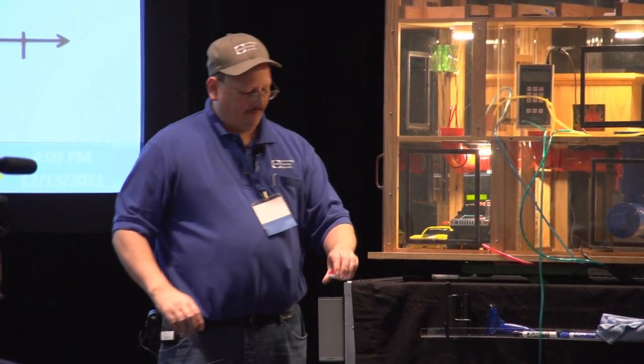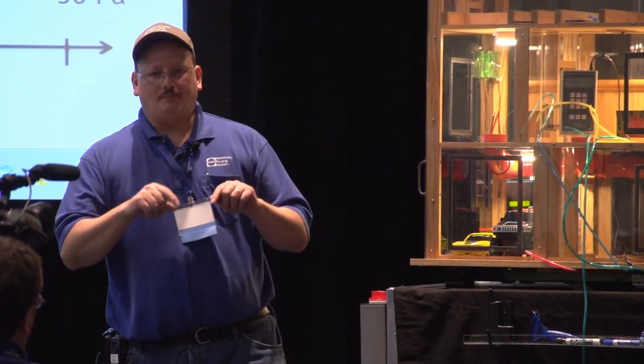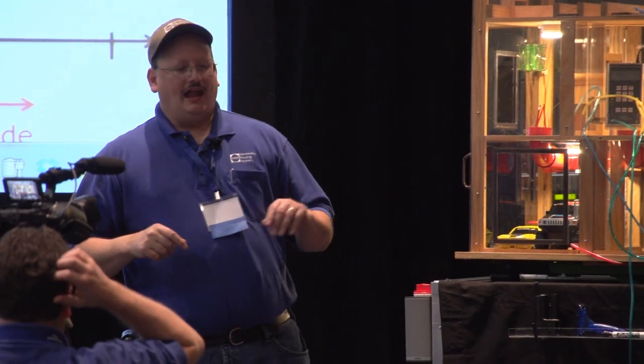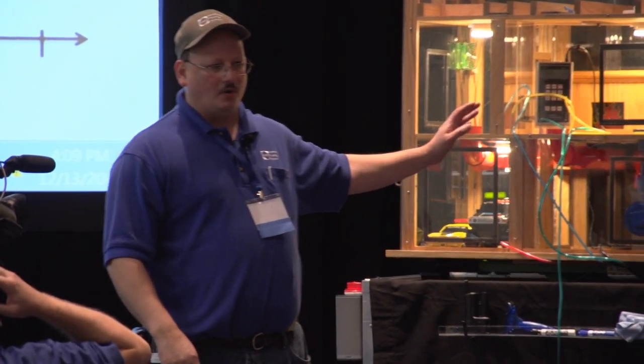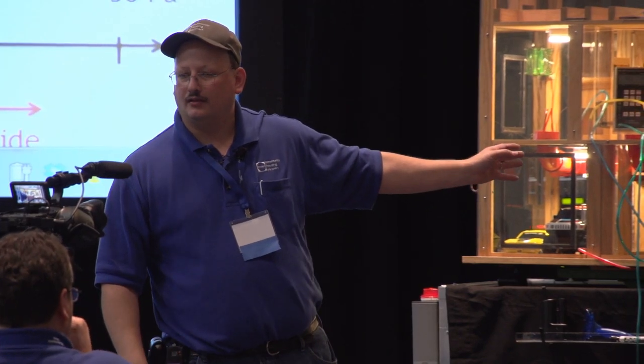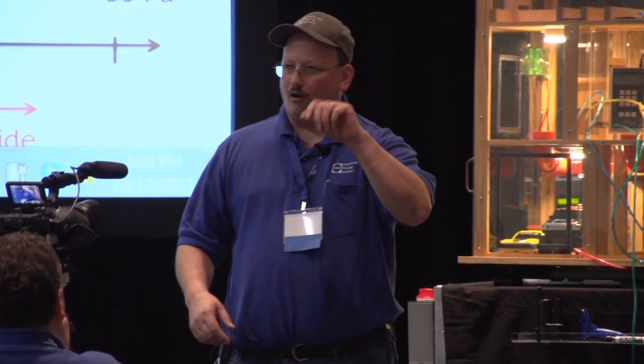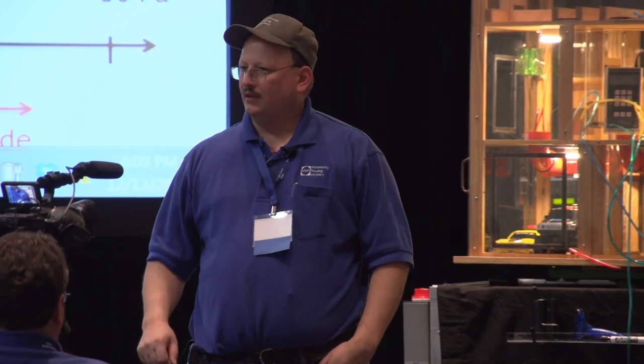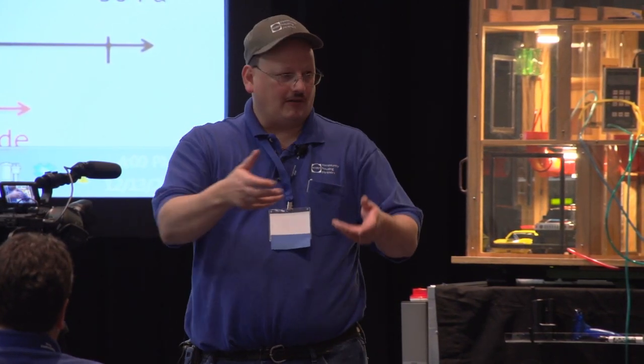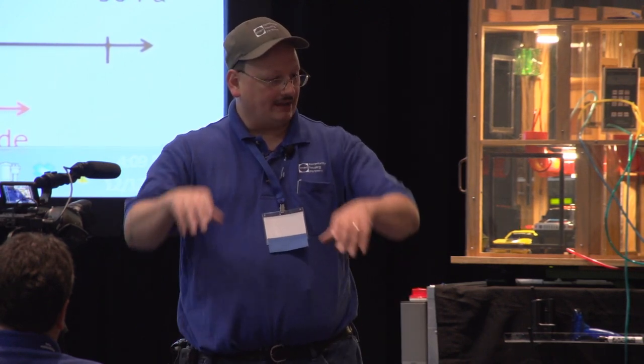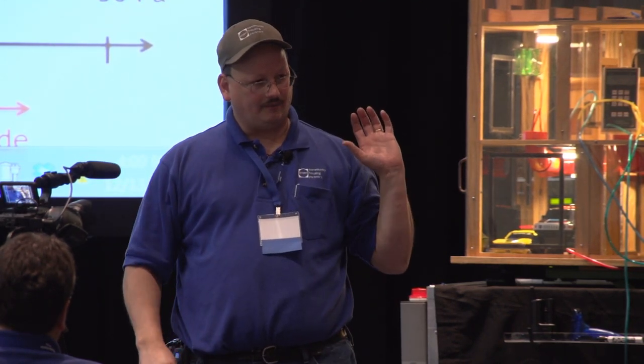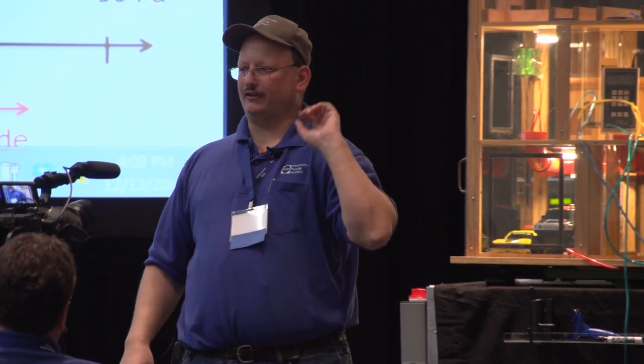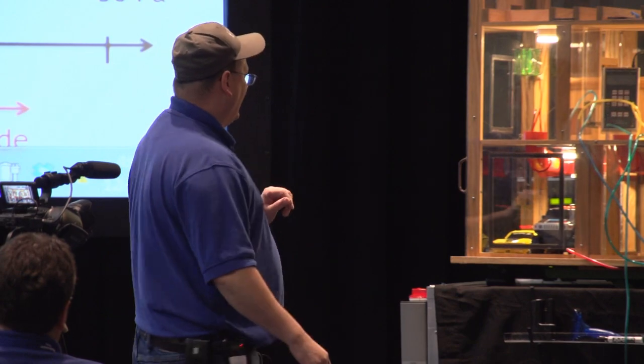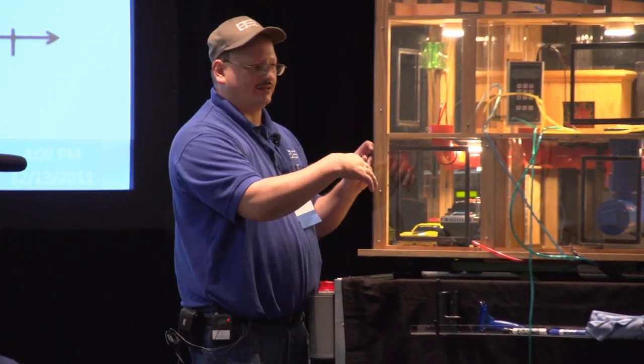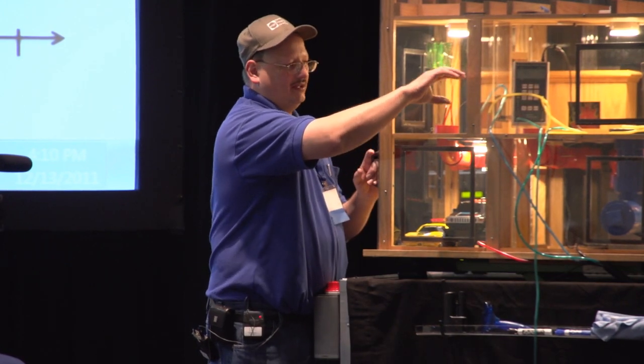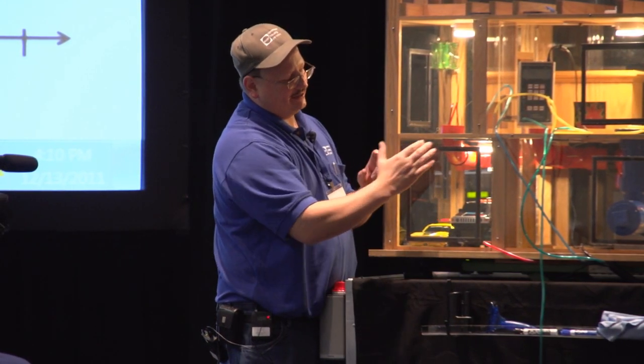And then, okay, while we're in the garage real quick, we're depressurizing the house, right? And we've got the door between the garage and the house open or closed at this point? It's closed. So you know how I was talking about going in the attic with the smoke puffer with the blower door on? Could you do that in the garage? So you could go in the garage, you puff the smoke, see where the air's coming. You got the door itself, you got your light switch boxes, all kinds of penetrations between that garage wall and the house. So if you're on the positive pressure side, in other words, it's negative inside the house, so it's depressurizing, that means that the air outdoors is going in.